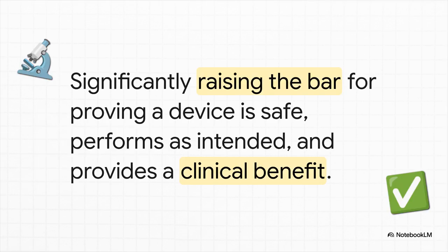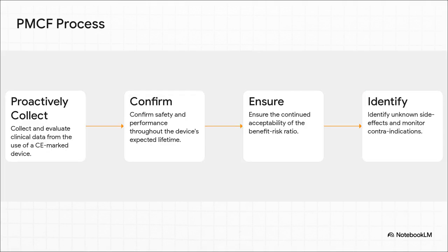And that brings us to our third pillar, which, frankly, might be the biggest game changer of them all: strengthened clinical evidence. The MDR raises the bar dramatically here. It's no longer enough to just say a device is safe. Manufacturers now have to prove that it performs as intended and provides a tangible clinical benefit. So getting a device approved is really just the beginning of the journey now. Under the MDR, manufacturers must continuously and proactively collect real-world data on their devices through what's called post-market clinical follow-up, or PMCF. This is an ongoing process to prove that the device remains safe and effective throughout its entire lifespan on the market.